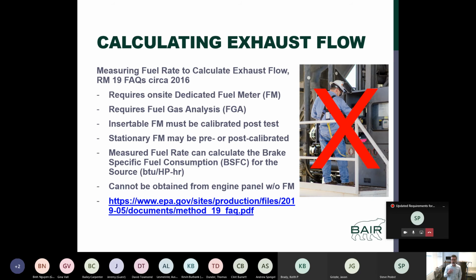There is an option we've used: insertable fuel meters on the day of testing, where we can tap into the fuel line and get those fuel meter readings directly there. If you're using an insertion type fuel meter, you need to provide a calibration at the end of the day for that fuel meter to show that it was accurately reading.